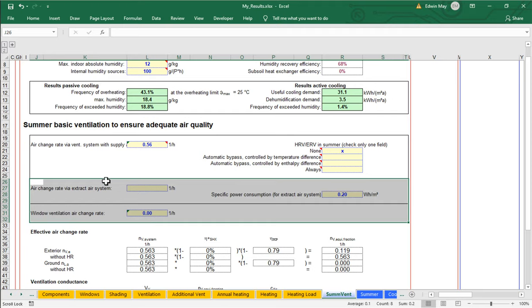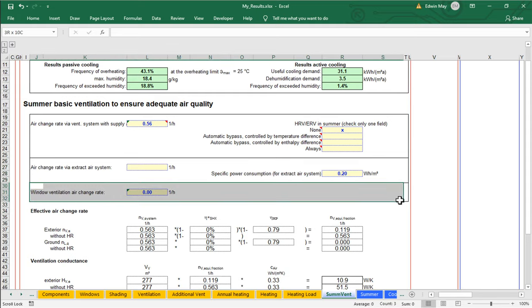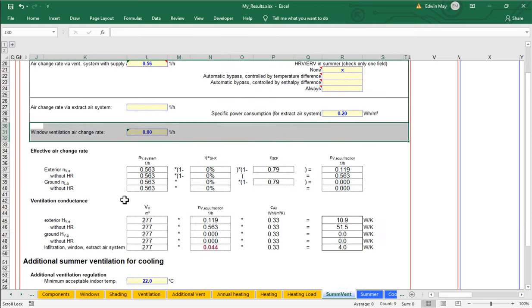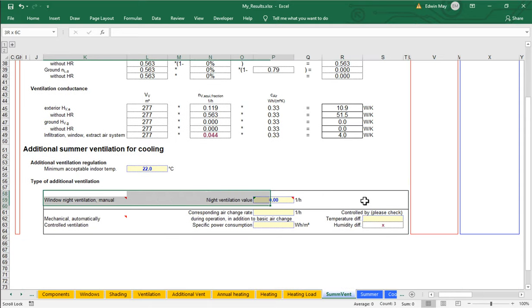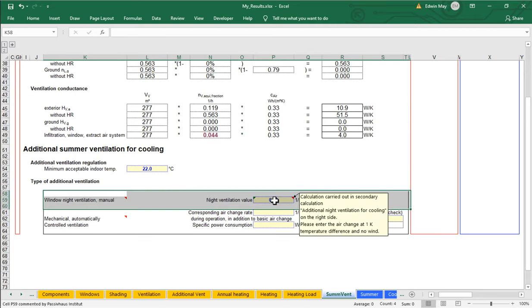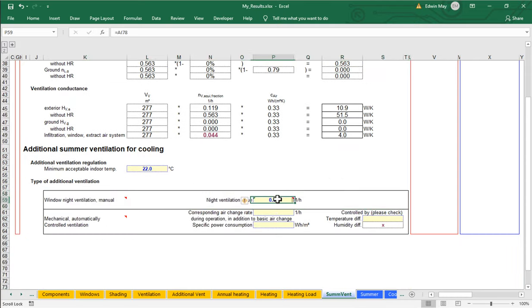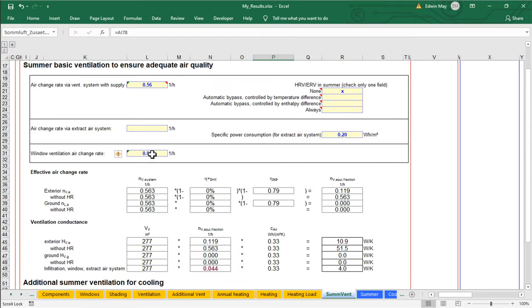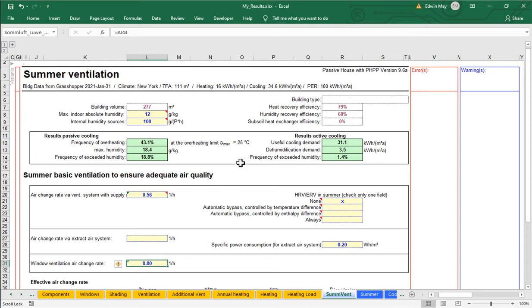So we can input some window ventilation information. I should also note, this is the daytime window ventilation. We have an additional input down here on the bottom for nighttime or extra window ventilation, and then we have even additional fan controlled ventilation below that. Currently, these are zeroed out. So we currently have no additional ventilation from our window systems, from our operable windows. As a result, we have a frequency of overheating of about 43% of the summer period, maximum humidity of 18 grams per kilogram, and a frequency of over humidity of almost 19%. Not very good.